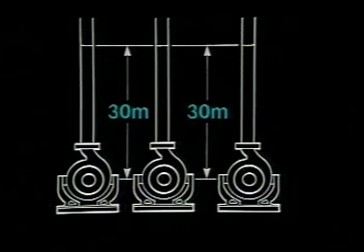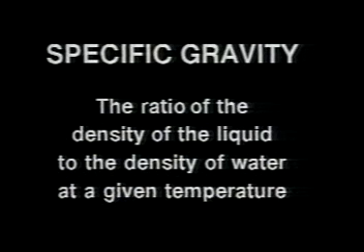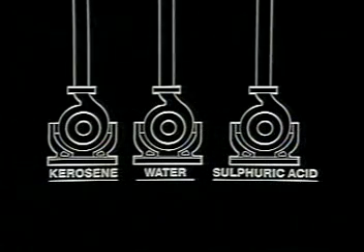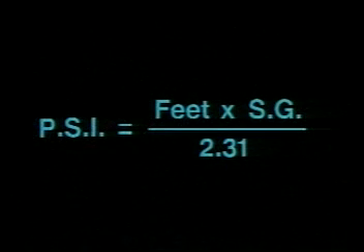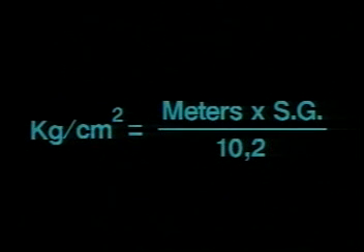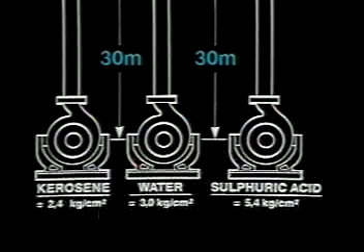Consider three identical pumps with the same impeller diameters running at the same speed, each handling a different liquid with a different density. Each pump will develop the same head of 100 feet or 30 meters, pumping kerosene, water, and sulfuric acid. Each liquid has a different specific gravity, defined as the ratio of the density of the liquid to the density of water at a given temperature. The specific gravities of these liquids are 0.8, 1.0, and 1.8. Head in feet can be converted to pressure in pounds per square inch by multiplying the head by the specific gravity and dividing by the constant 2.31. Pressure in kilograms per centimeter squared equals the head in meters multiplied by the specific gravity, divided by the constant 10.2. Thus, from the same head on three different liquids, three different pressures are created.